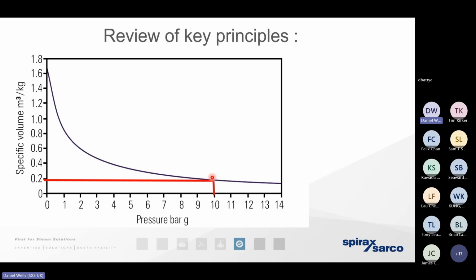And then, for reasons we've gone through in previous presentations, we depressurize the steam as close to the point of use as possible. One benefit is that the steam's going to move in accordance with the pressure drop around site. We don't need to pump it. We can keep the infrastructure small by reducing the steam at the point of use. We can manipulate the pressure to control the temperature. But it also tells us that by depressurizing the steam, it's going to expand, and therefore we can get it across the heat exchanger surface area very quickly. But we need to remember that when we've depressurized the steam, it is going to want to expand. So the pressure-volume relationship really tells us that if we know the pressure of the steam, we know the volume it's going to occupy.